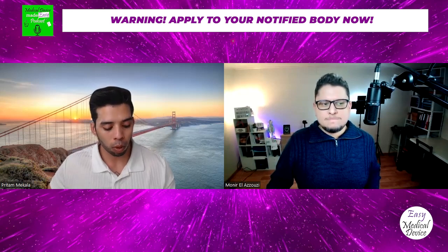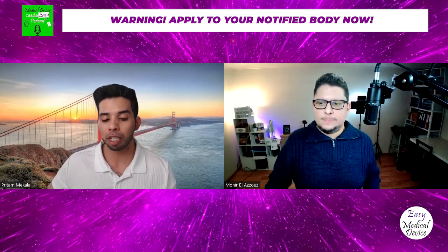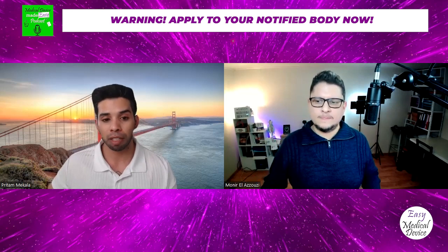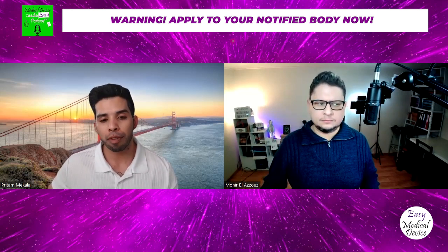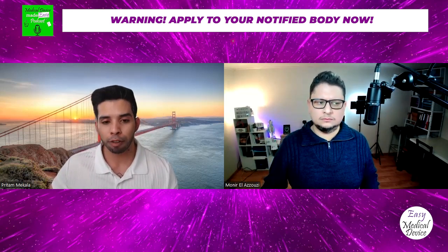Absolutely. Well, there are a couple of other things you can discuss with a notified body. You can also discuss the pace of the review, right? A standard review timeline could be longer for some devices and some businesses, but you can definitely pursue a faster timeline. You could do an expedited timeline, you could do a dedicated timeline, and so on. We certainly offer that, and I'm sure other notified bodies do as well. So I would say, definitely ask those questions.